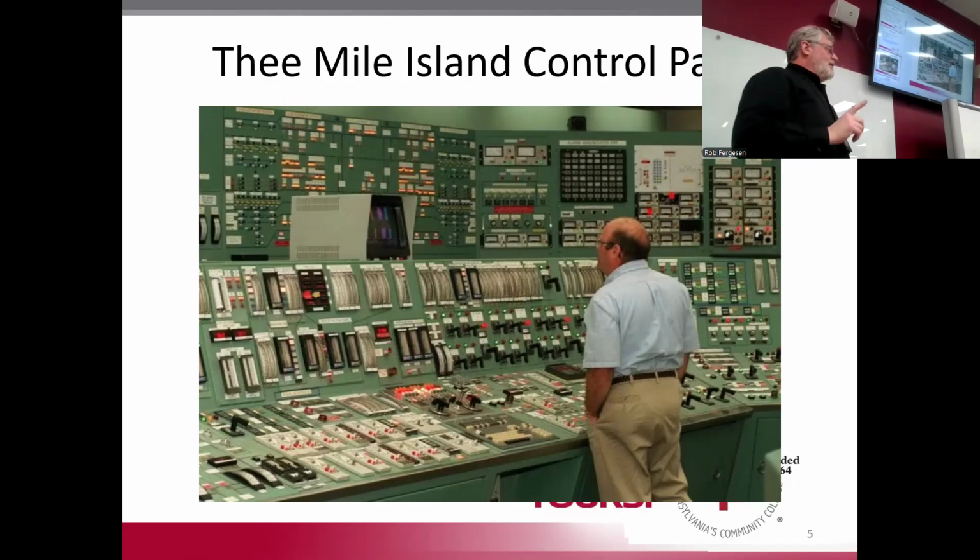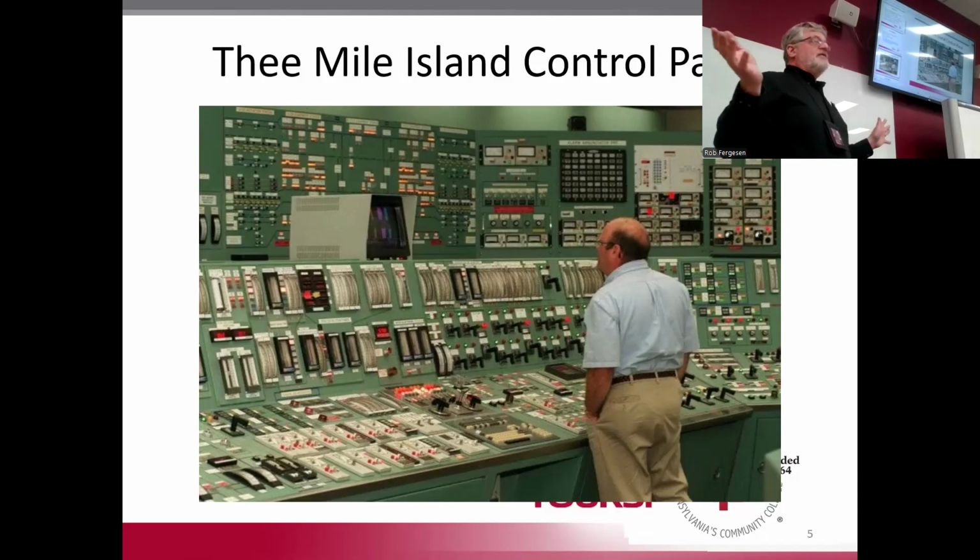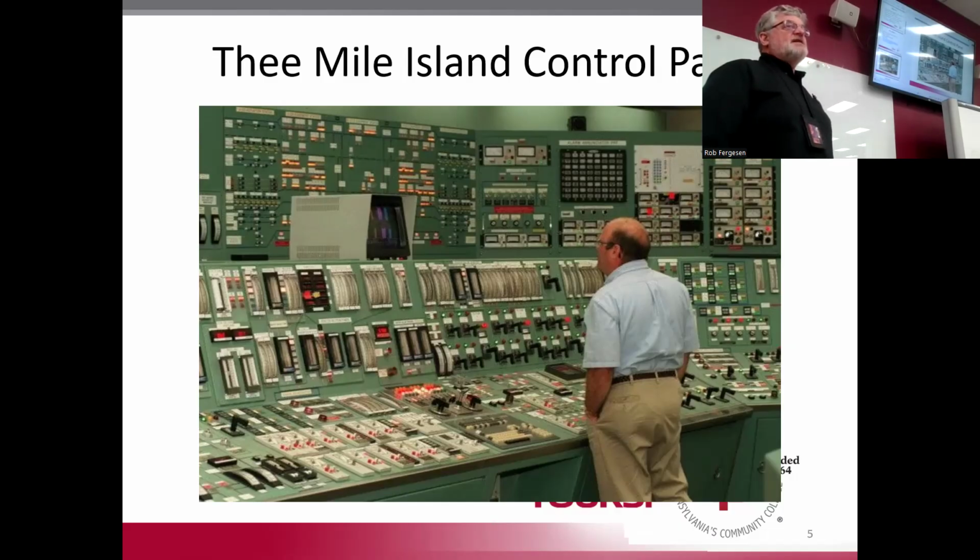But at Three Mile Island, when they had their reactor meltdown, what happened was one pump failure led to an overheat, led to another failure, to an overpressure failure. They had a cascading set of failures from one source cause. But when that operator rolled into the control room and looked up at his control board, he saw nothing but flashing lights and beeps and buzzes, and I think half a dozen different alarms were showing by the time he rolled in there. How is he supposed to address that situation?